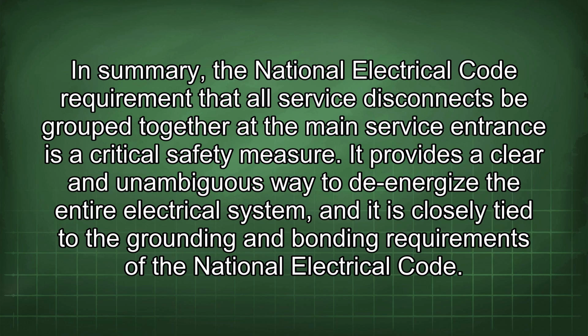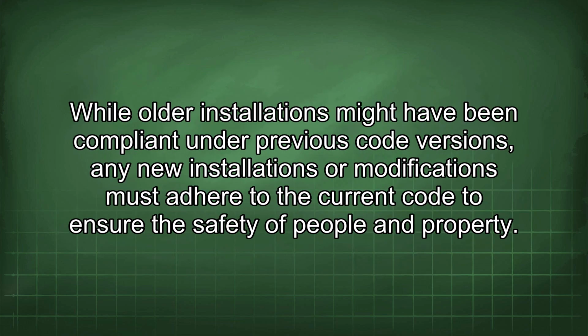In summary, the National Electrical Code requirement that all service disconnects be grouped together at the main service entrance is a critical safety measure. It provides a clear and unambiguous way to de-energize the entire electrical system, and it is closely tied to the grounding and bonding requirements of the National Electrical Code. While older installations might have been compliant under previous code versions, any new installations or modifications must adhere to the current code to ensure the safety of people and property.